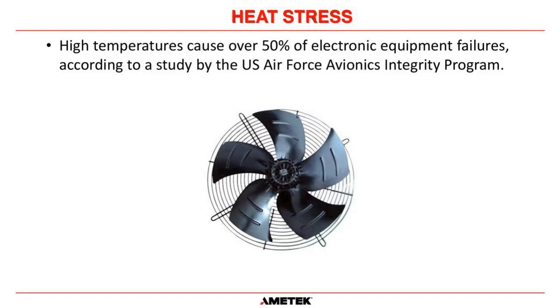So all of our UPSs have been designed in such a way that we know how much air we need to get out of the system to make it run at the temperatures that we have designed. So we will have fans on the heat sinks for the power semiconductors, for the SCRs and for the transistors. And if it's a bigger UPS, we will also have fans on the top of the UPS to pull even more air out, because there are going to be bigger transformers. Magnetic transformers do dissipate a lot of heat also, and we need to get that air out of the UPS so it doesn't heat up all of the components inside the UPS and cause premature failure.